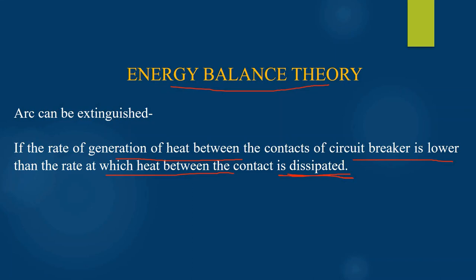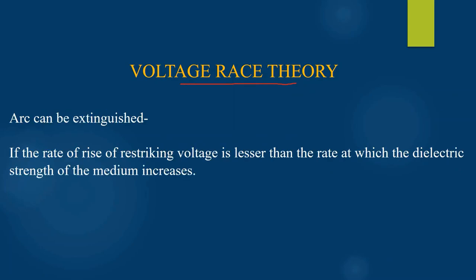According to the voltage race theory, the arc can be extinguished if the rate of rise of the re-striking voltage is lesser than the rate at which the dielectric strength of the medium increases. To achieve this, ionized particles are caused to recombine into neutral molecules — in this way there will be fewer ionized particles between the two contacts of the circuit breaker. Also, by removing the ionized particles and replacing them with unionized particles, we can increase the dielectric strength.